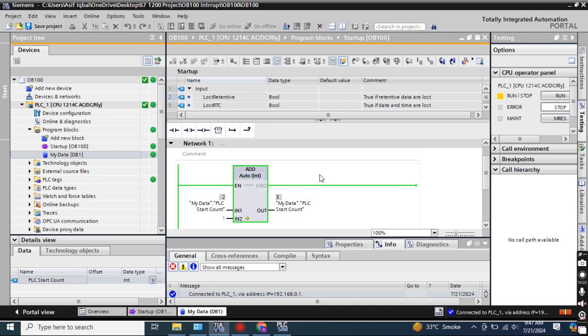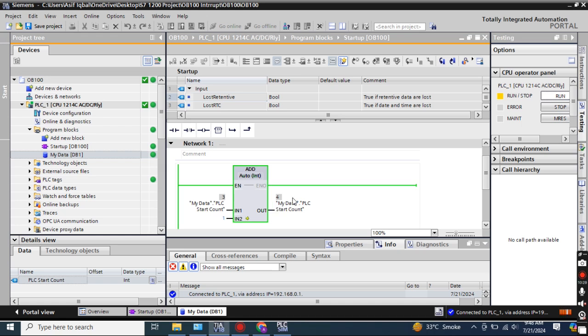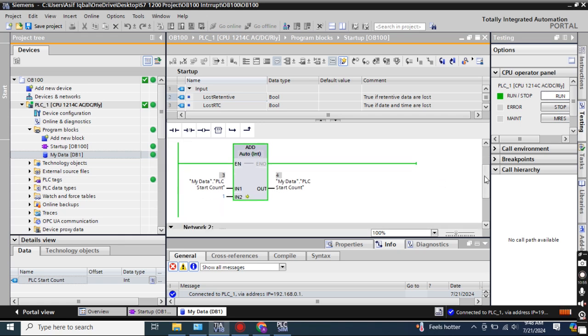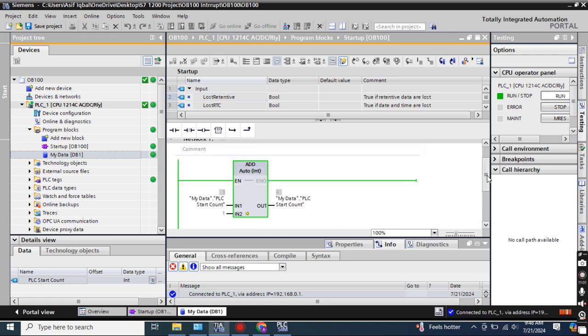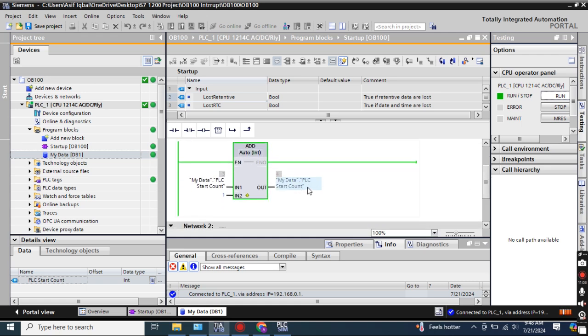Now again I make it Stop — and the count is 4. In this way, you can count the number of times your PLC has started. On this event you can also do some initialization — set counter, timer, or encoder values. You can also create alarms to display on your front panel, HMI, or SCADA system using this bit, or configure anything you want based on the value change of this address.